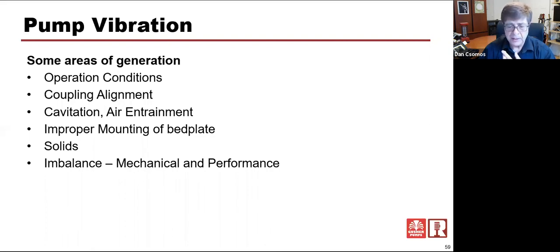We had a pump at Honda Anna, an engine plant in Ohio for Honda Motors. And as the system was built, somewhere along the line in construction, a piece of 2-inch angle iron, 18 inches long, got into this tank. And we had a 6x8-15, two of them actually, in a pump back tank that were drawing liquid out of the bottom of this tank.